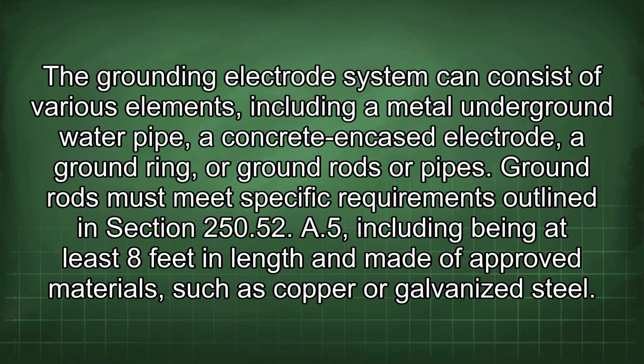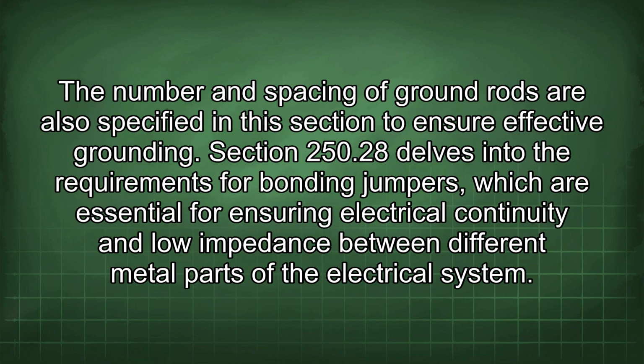The grounding electrode system can consist of various elements, including a metal underground water pipe, a concrete encased electrode, a ground ring, or ground rods or pipes. Ground rods must meet specific requirements outlined in Section 250.52(A)(5), including being at least 8 feet in length and made of approved materials, such as copper or galvanized steel. The number and spacing of ground rods are also specified in this section to ensure effective grounding.